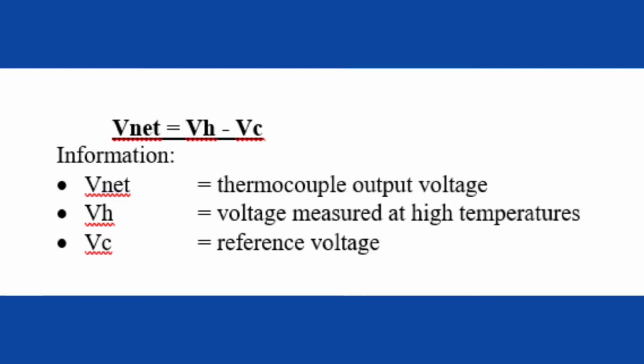When the thermocouple is used to measure high temperatures, a voltage will appear as large as VH. The real voltage is the difference between VC and VH, called net voltage or Vnet. The magnitude of Vnet is determined by the formula. Vnet is thermocouple output voltage. VH is voltage measured at the high temperatures. VC is reference voltage.